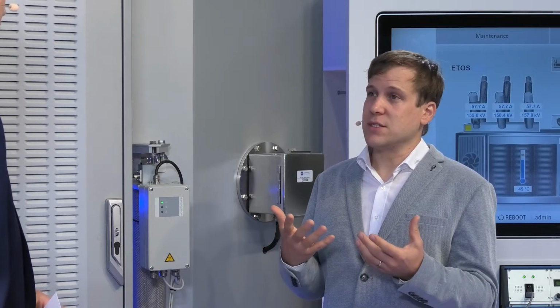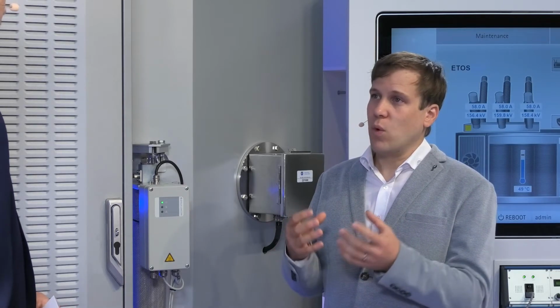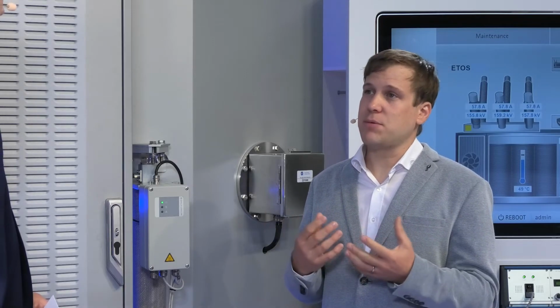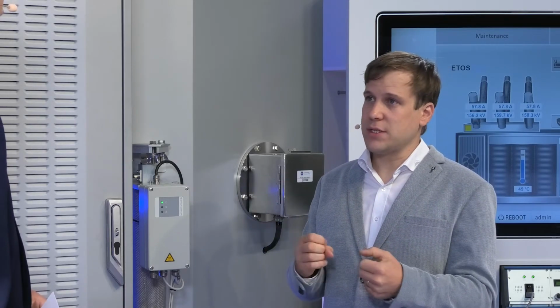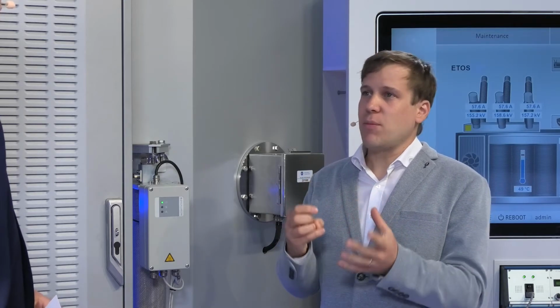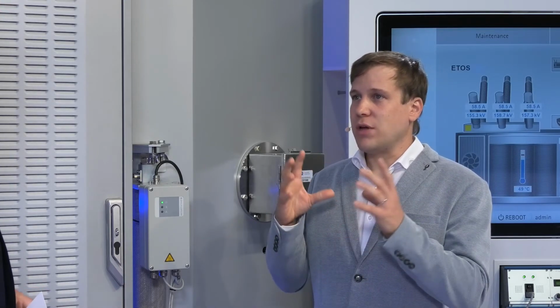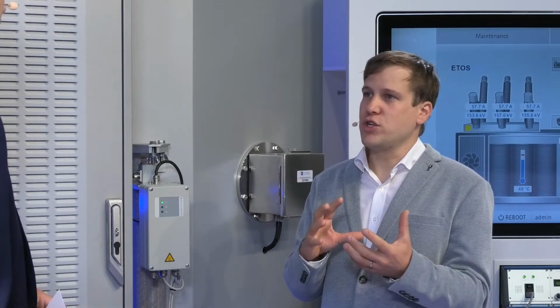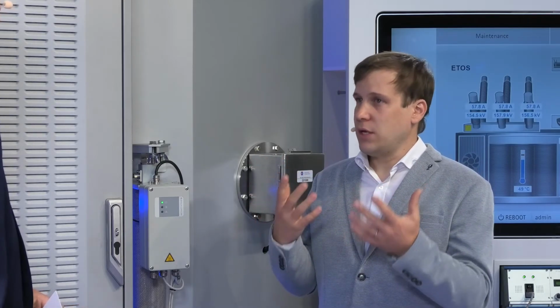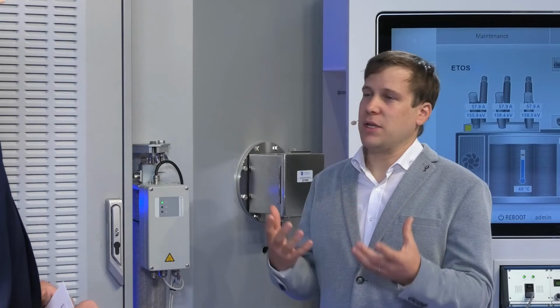It requires certain information, where we need that fingerprint from the factory where we measure that exact system. But we have a brand new system here as well, the so-called MSense VAM, the vibroacoustic measurement. Therefore, we only need one sensor on top of the tap changer cover. You take out one screw, install that sensor. That's basically it. And this is a high precision microphone. It listens closely to every noise of the tap changer during the operation. If something changes here, it will inform the customer about that change so that you can take further actions like maintenance as well.